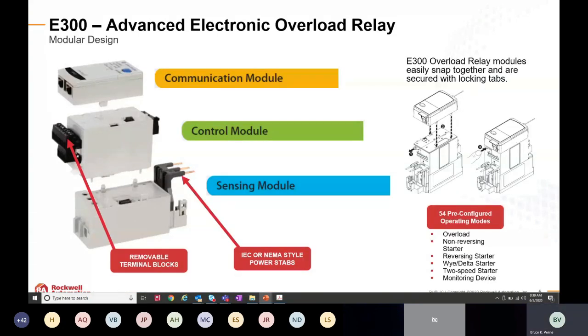The E300 is comprised of 3 different types of modules. At the top, as seen in previous presentations, is the communication module, offered in the form of Ethernet IP, DeviceNet, or the E200 with a USB connection. In the middle is the control module, essentially the brains of the operation, where all the parameters and the microprocessor of the overload component sit, and where you have access to all the different I/O.